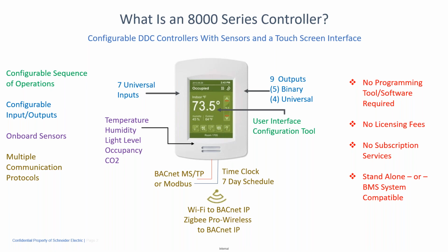These also have multiple communication protocols that can be utilized. On board is BACnet MSTP or Modbus, and you can toggle between the two of them. You could add a device that will add Zigbee Pro wireless communications, or you can have Zigbee Pro wireless built into the device itself, or you can add a card for Wi-Fi communications. If you choose not to have a communication protocol, not part of a network, they do have a time clock and schedule built into them.